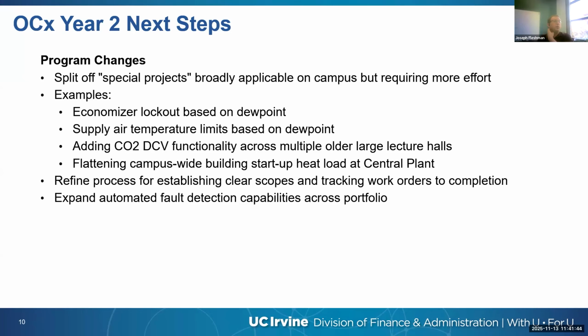Like I mentioned, we're near the coast, so one of the challenges we have is on really humid days a dry bulb economizer lockout isn't sufficient, because we basically dump tons of humid air into the building. So we're looking at supply air temperature limits based on dew point, and economizer lockout based on dew point. One of the last things we're challenged with is that building startup heat load really hits the central plant hard, which is a challenge for the plant to manage - we really want to flatten that heating load in the morning.